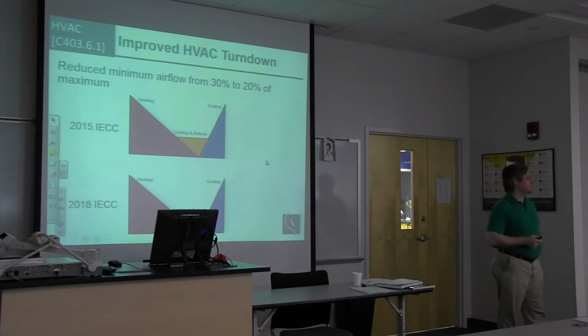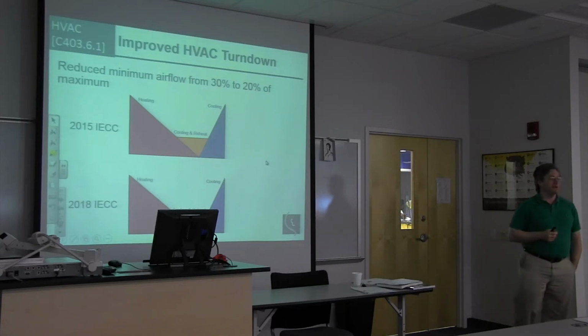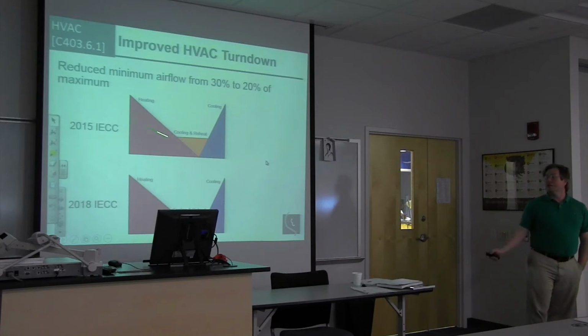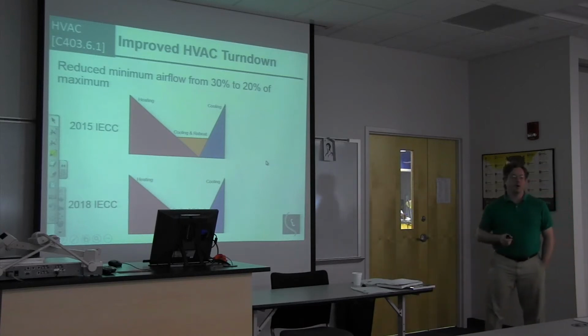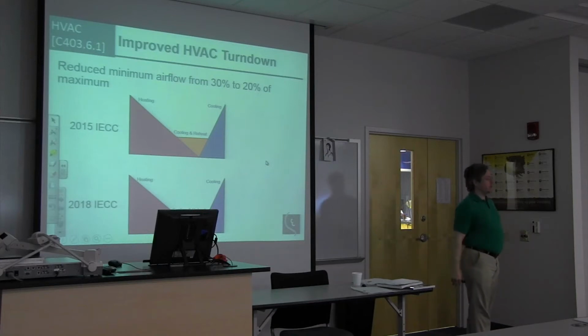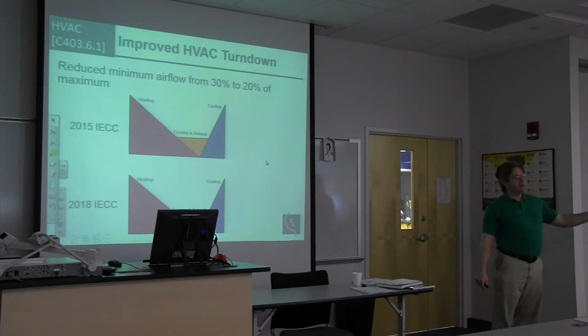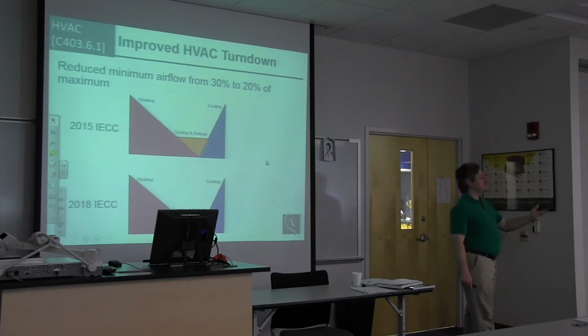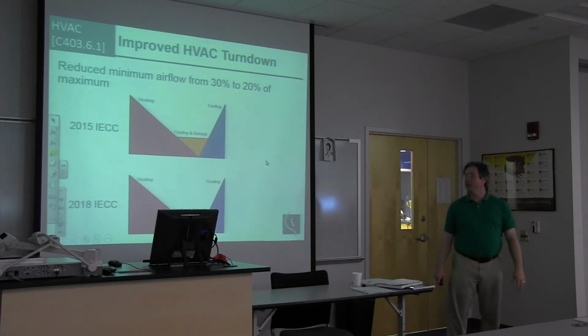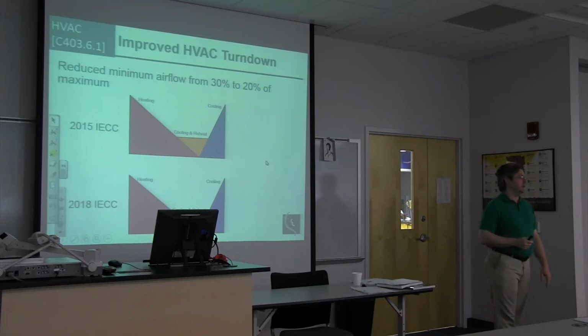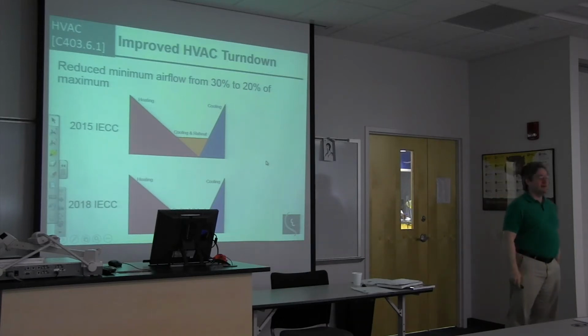Airflow for VAV systems, reducing the minimum airflow from 30% down to 20%. In this orange triangle down towards the bottom, this is where you are overcooling and then reheating. So I'm now paying to move the air, I'm paying to cool the air, and I'm paying to reheat the air, and then putting it back into the space. So I paid three times to have no real added benefit. So as you can tell, the area of that orange triangle diminishes substantially just by going from a 30% turn down to a 20% minimum airflow.